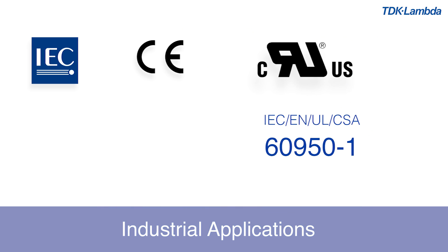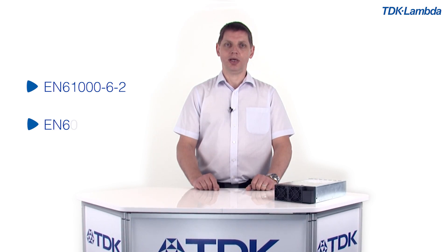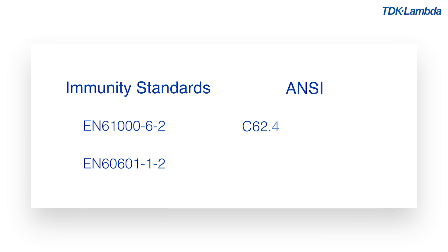We have also ensured that the entire range is ideal for industrial applications by approving it to IEC, EN, UL, and CSA 60950-1. The whole range is also designed to meet IEC and EN 61010-1. Compliance with EN 61000-6-2 and EN 60601-1-2, and also the TUF ANSI C62.41 Level 2 3kV ringwave, help to make your system more fault tolerant.